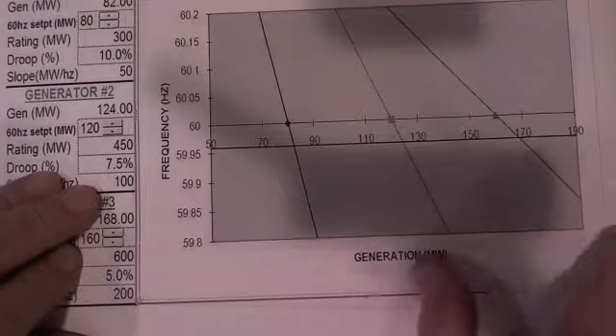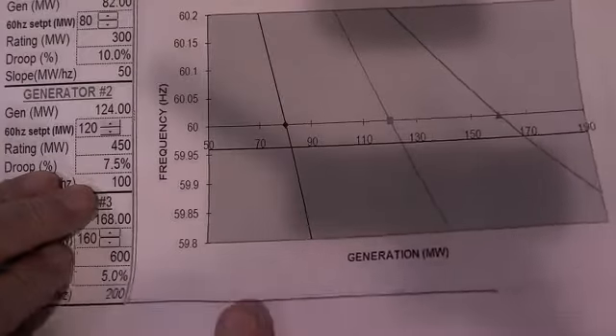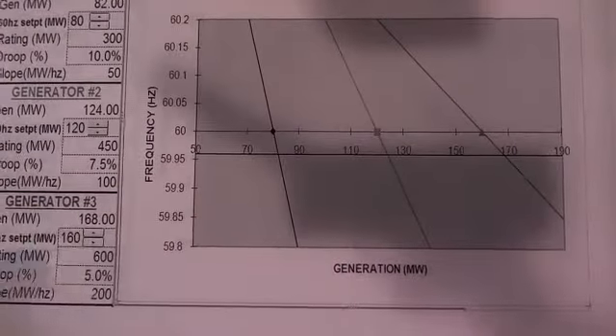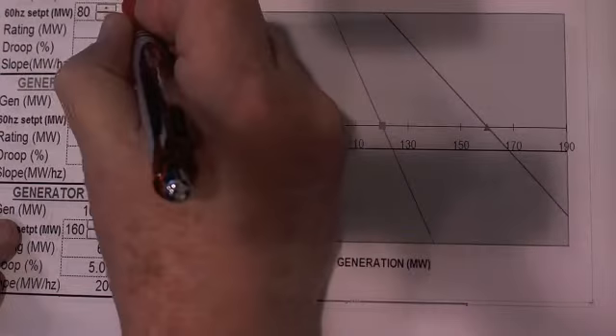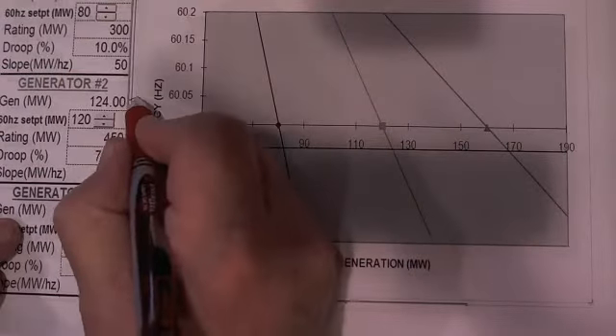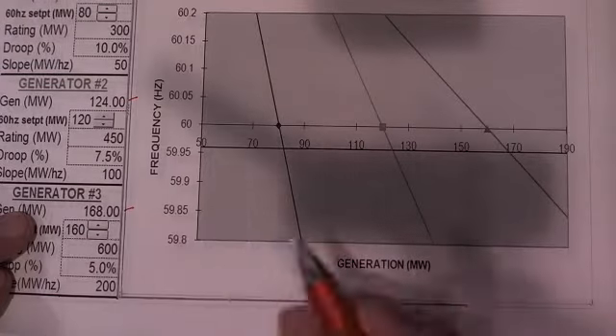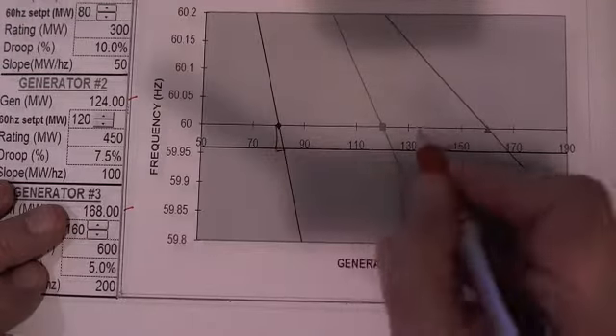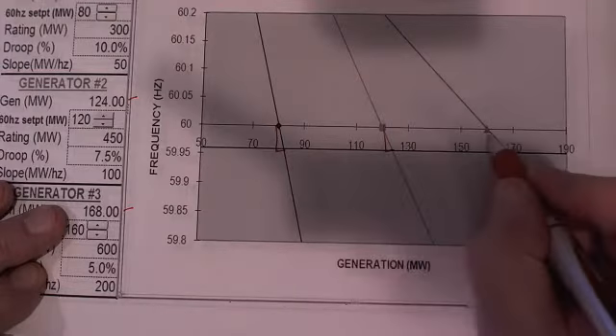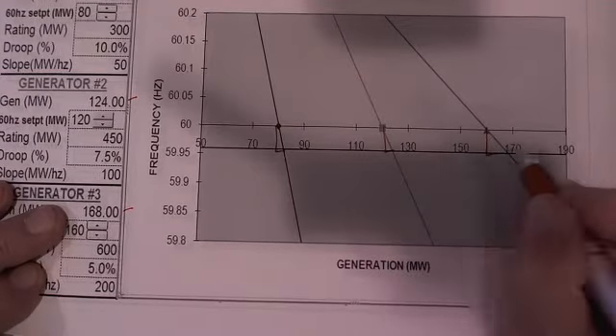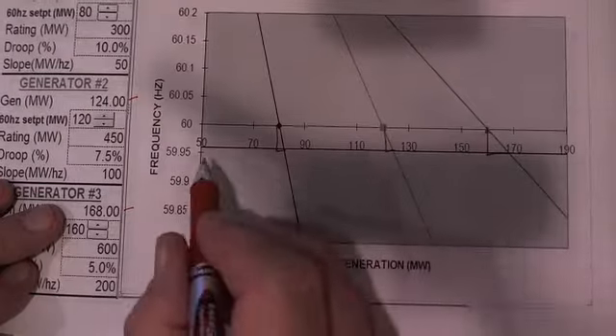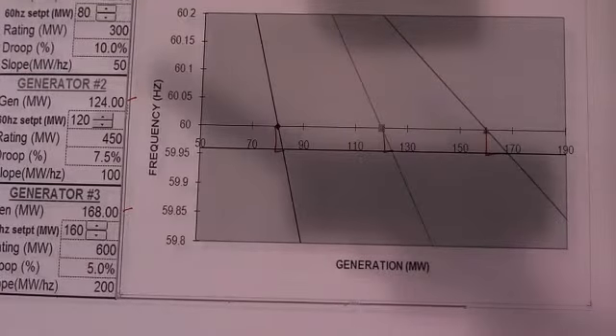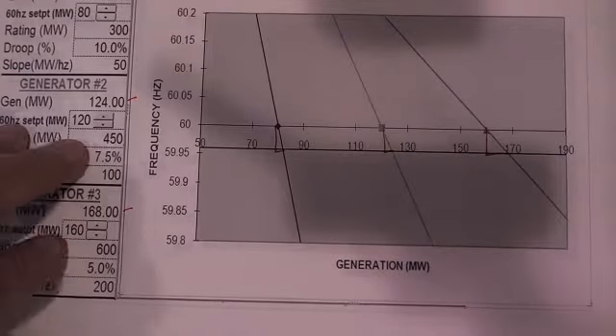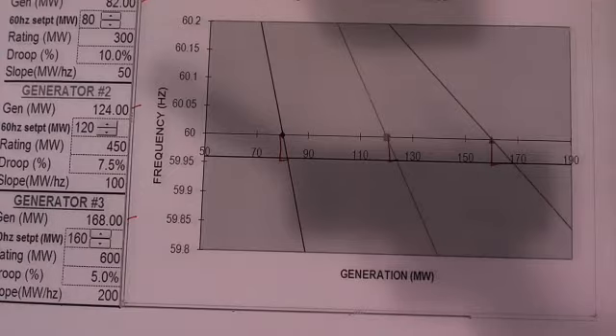If it went to 374, so now we've increased by 14, we pick up 2 here, we pick up 4 here, that's 6, and we pick up 8 here. So it's just different, and you can see that the frequency has dropped much further to accommodate a larger load increase. So once again, the load goes up suddenly, the generators will go up.